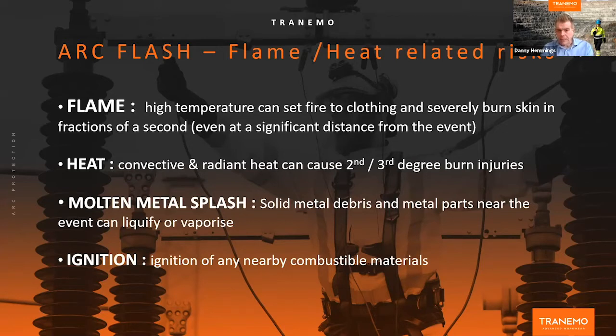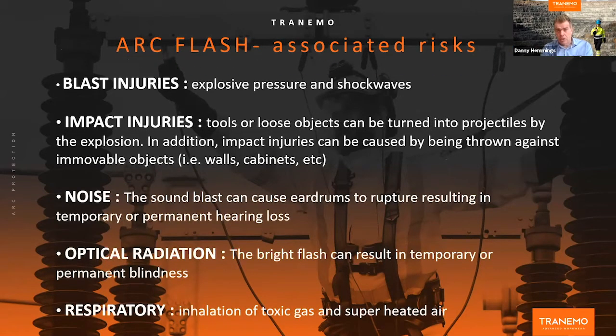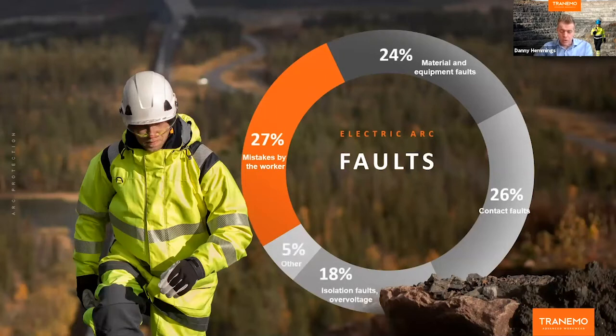And some examples of that: molten metal splash, so metal debris, metal parts can liquefy or vaporize within an arc flash. Ignition risk of any nearby combustible materials post arc flash. Blast injuries to a worker from pressure and shock waves. Impact injuries from tools or loose objects that can be effectively projectiled from an arc flash. Also impact injuries from being effectively thrown into an immovable object, such as a wall behind where the operative is working. Noise, intense noise levels, so that can cause damage to hearing. Optical radiation, which can cause damage to the eyes. Respiratory hazards, which can come from the inhalation of toxic gas and also superheated air. So there's a whole host of hazards that go with being on the wrong end of an arc flash.